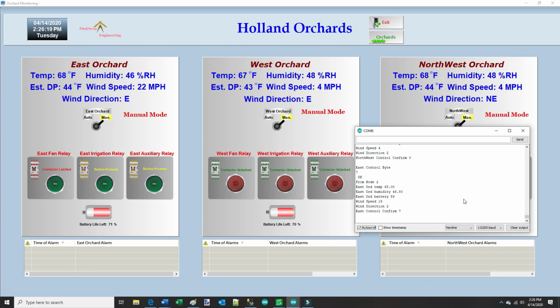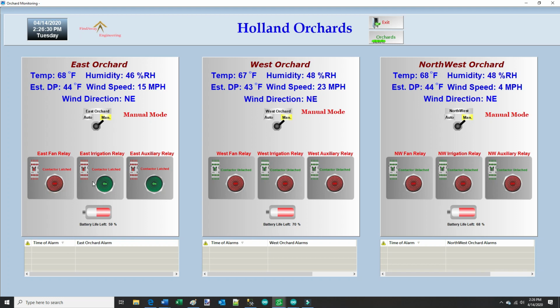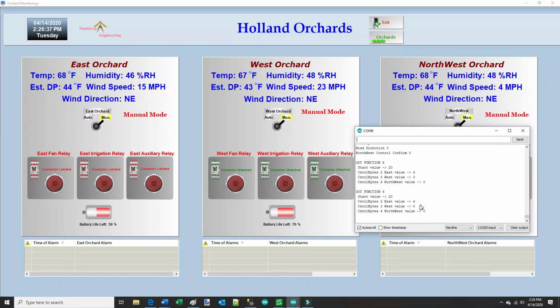And there you heard all 3 of those contactors latch, and we got a confirmation that they indeed are latched. So if I go ahead and turn these off, we should decrement those values, and you can see it going down here, 4, and we're at 0. So now all we're waiting for is the sensor node to pick up that transmission. You can see it's 0 here. We're getting west control. See, these sensor nodes have not acknowledged the transmission from the gateways yet either. So there you hear the contactors unlatched, and we get a confirmation back as 0, so those go to unlatched.